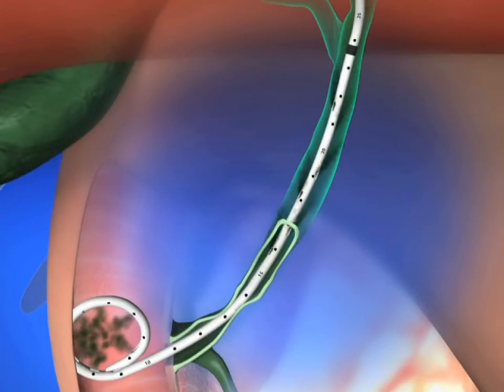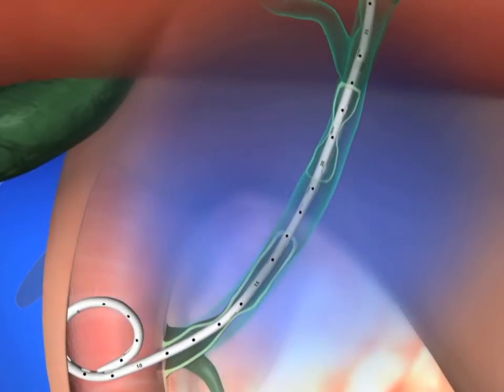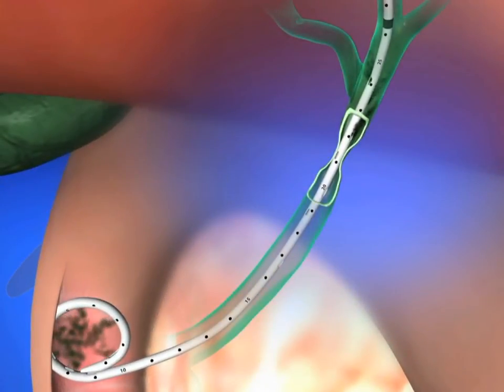the Resolve offers drainage catheters with holes that are more distal for lesions closer to the ampulla, and more proximal for lesions that are closer to the liver hilum.